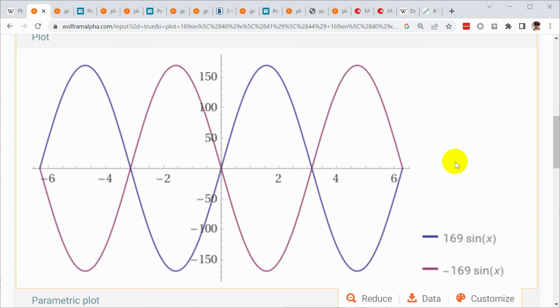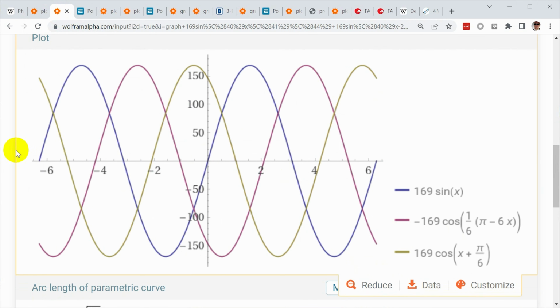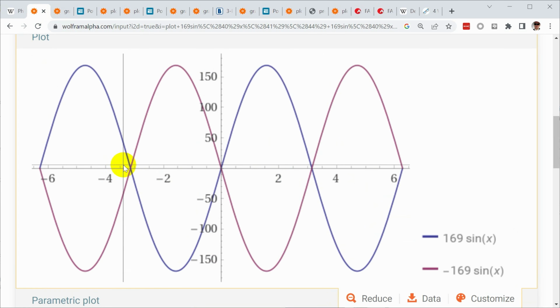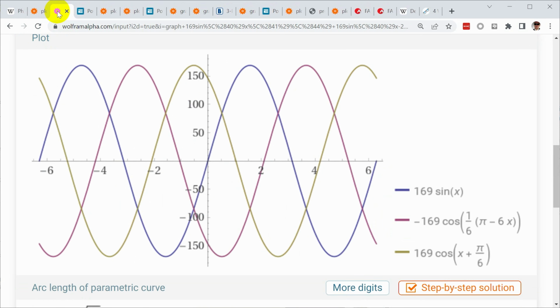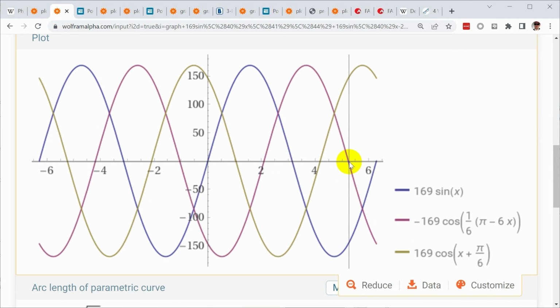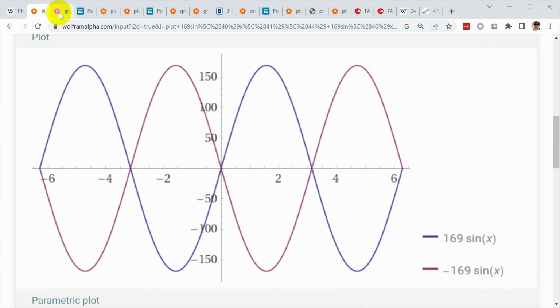So the job of the rotary phase converter is to convert our two input phases that are 180 degrees apart, or a single input phase, we'll talk more about that in a minute, into a three-phase output that's spaced at 120 degree intervals. Now, how does it do this? It doesn't seem intuitive. How do you take something that's 180 degrees out of phase and change it to something that's 120 degrees out of phase? You can't do that, especially since it's passing through the input to the output.